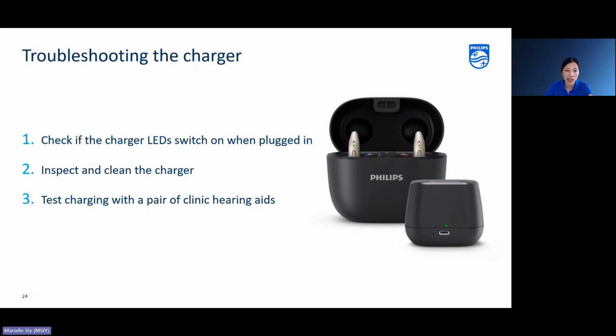So if there's no LED light, as you see on this picture, it's time to have it replaced. If the charger is switching on, then the next step is to inspect it for any damage and clean the charger, including the two contact ports. Those are the two holes there. Once they're cleaned, try charging the user's hearing aid and then test the charger with a pair of clinic hearing aids. Try charging for 15 minutes. If the hearing aids are still not charging, then the charger will need to be sent back for repair.